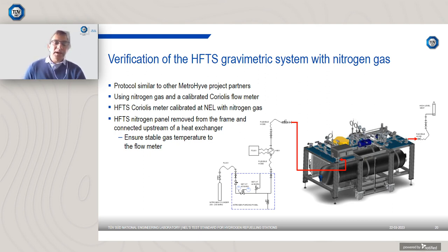So in this case, what we have done is to use the same nitrogen panel that we have on the test rig for purging it. But the difference in this case is that we have also included a heat exchanger, and this was based on the findings from the other project partners. Essentially, what they found is that in order to get more repeatable results, it was best to have nitrogen gas coming into the flow meter at a constant temperature. Hence the reason for installing a heat exchanger, to ensure that we, in our case, had 20-degree nitrogen gas coming into the Coriolis flow meter.